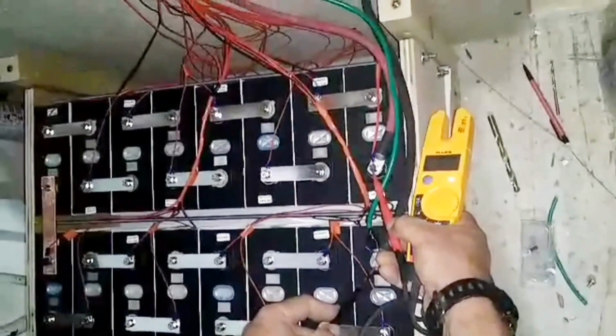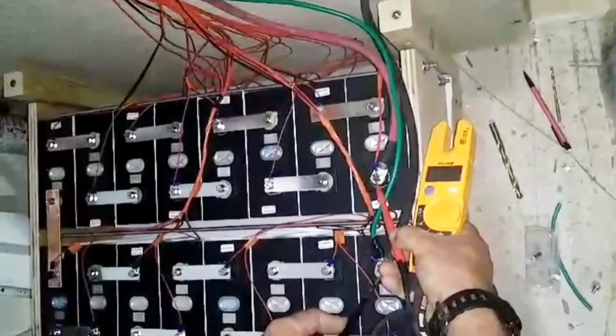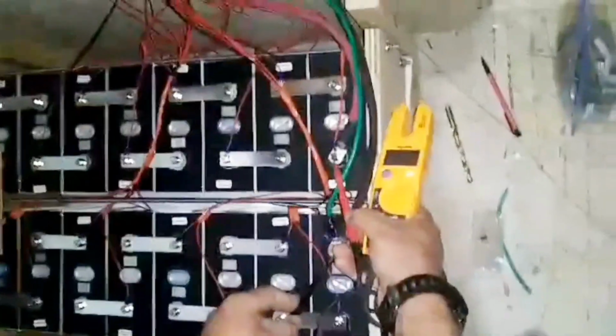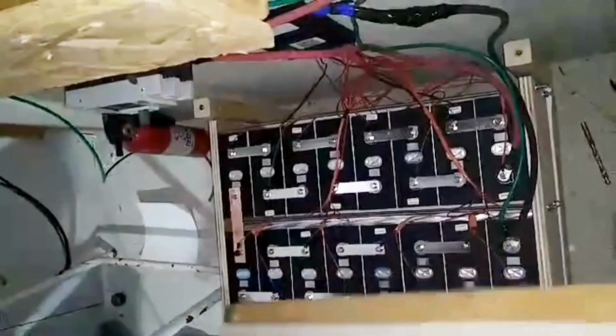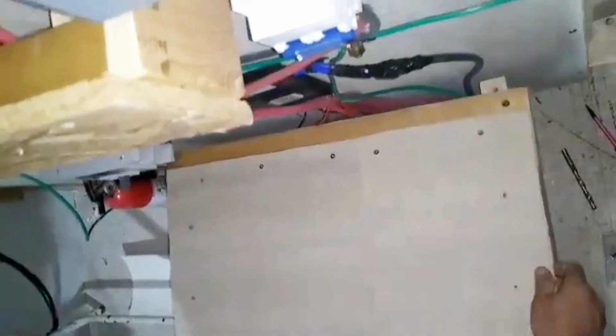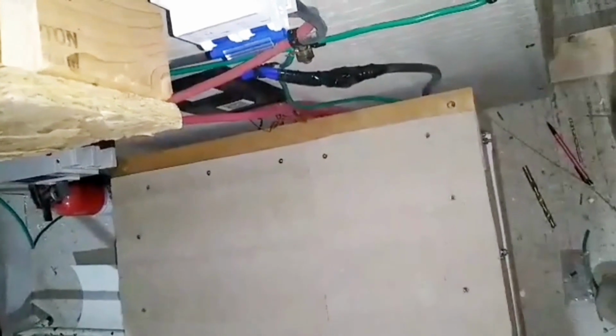So the breaker is in the off position now. If you put a voltmeter across here, you can check your voltage, and you can see I have 52 volts. So just checking my polarity - it's really important before you close breakers that your polarity is correct. I'll get this on for safety, and then I'll be ready to fire up the system.